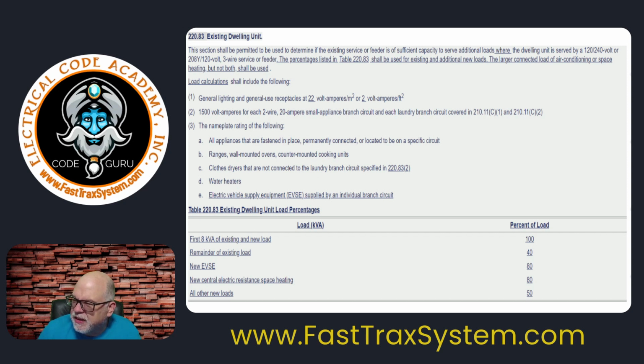Now, how do you apply this? Look at the bottom here. Here's where it's different. First 8 kVA of existing and new loads, 100%. So the same thing, first 8 at 100%. So it's going to be 8 kVA to start off, right? The remaining of the existing loads at 40%. Then, if you're adding any new EV to this, notice it says new EV. So if you're adding new EVSE to this, you take it at 80%.